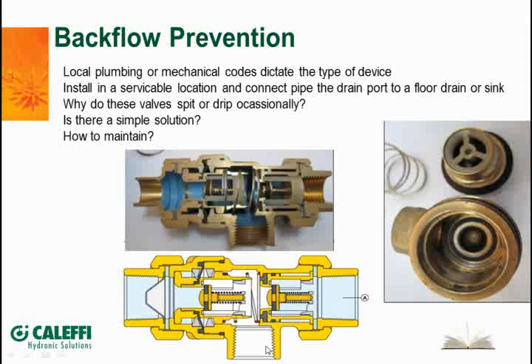Notice, first of all, that they're threaded down here on the discharge port, and they're threaded because we want you to put a fitting in there and take this discharge down to a drain, ideally, or at least down to the floor where they're not going to drip over the top of expensive equipment. When I saw these valves installed in Europe, they actually have a little funnel that bolts on the outside of this with a little set screw, and so it gives them a little air gap protection, and they take that right down to a drain.